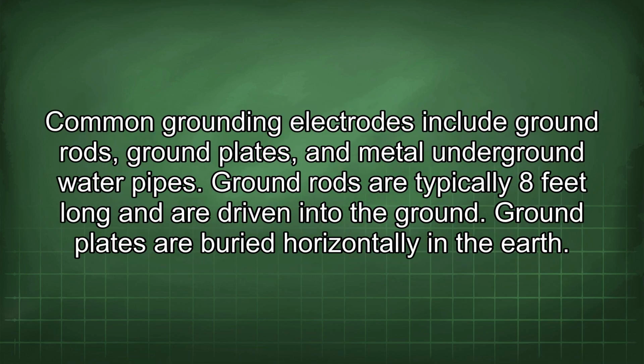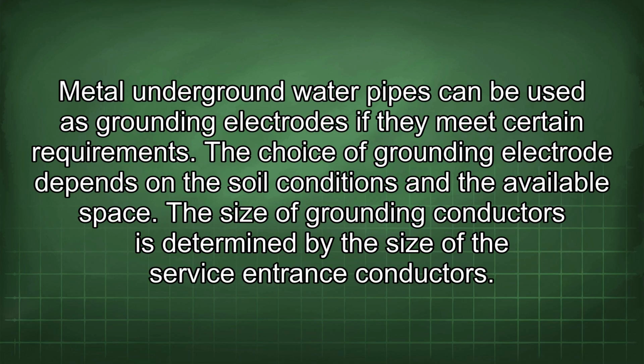Common grounding electrodes include ground rods, ground plates, and metal underground water pipes. Ground rods are typically 8 feet long and are driven into the ground. Ground plates are buried horizontally in the earth. Metal underground water pipes can be used as grounding electrodes if they meet certain requirements. The choice of grounding electrode depends on the soil conditions and the available space.